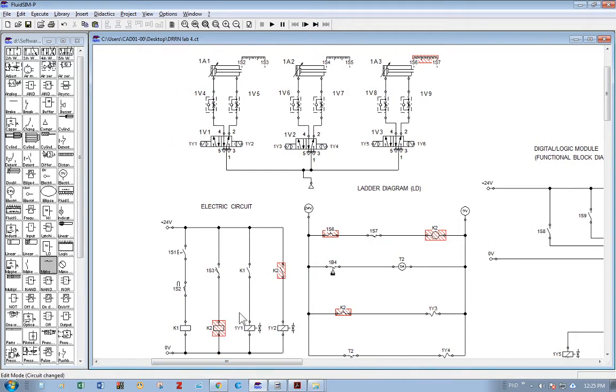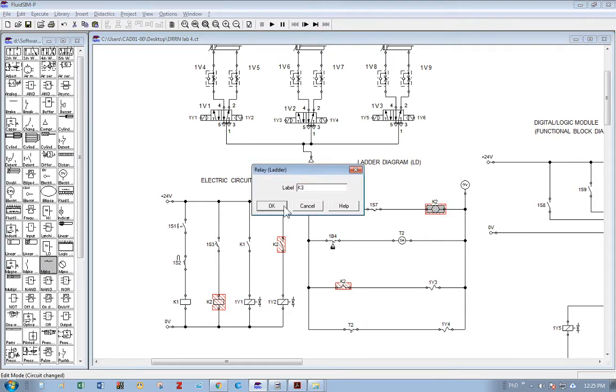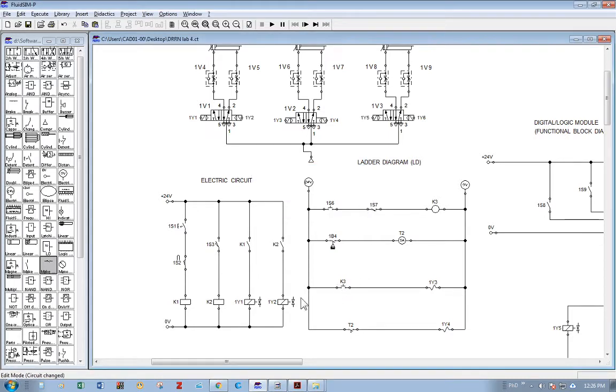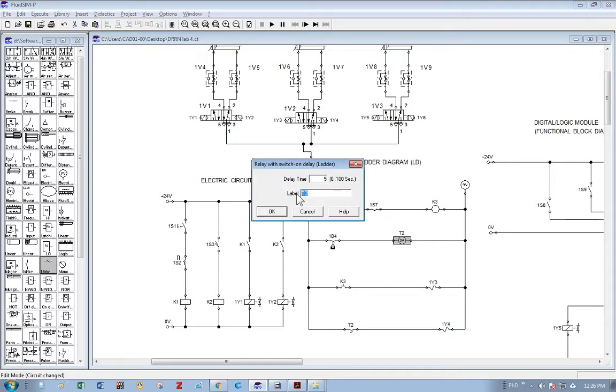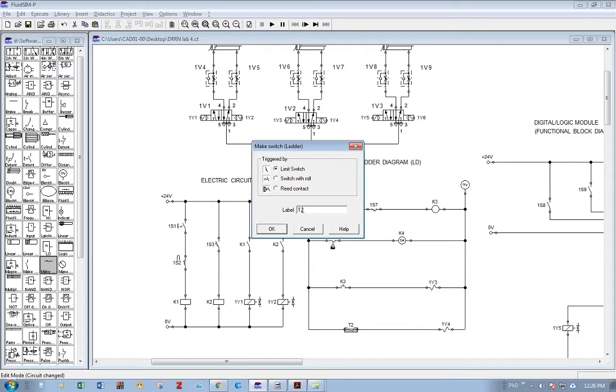First, we need to identify that there are no repeated labels. We have a relay called K1 and K2, but in the second circuit we have K2 again, so I need to change that label to K3 and change the corresponding contact to K3 as well, avoiding any repetition. Relay K1, relay K2, and then relay K3. There is also a relay labeled T2 — although not wrong, the better labeling procedure is to use the K symbol, so I'll relabel it K4 and update its corresponding contact to K4 as well.